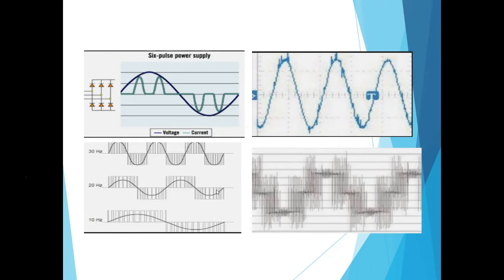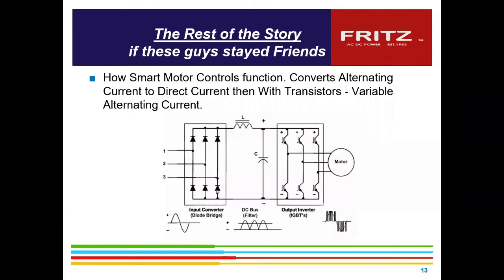So it's just knowing that when you're changing a circuit from what existed, the motor before was just connected with a contactor turned on and off, and basically allowed to run up to full speed, whatever the sine wave was, try to get it to 65, but that's why you get a big surge in current and power. Well, that doesn't happen when we can regulate this and slowly ramp the voltage and frequency up to the motor.